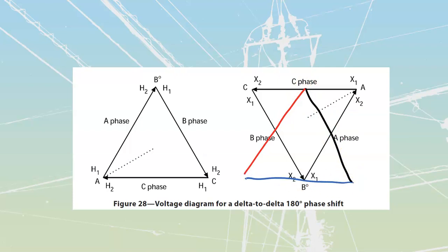If I take a look at that, I now see that on a standard system, here's where my line A is, and now I'm going all the way across from there to there if I were trying to parallel these together. This is going to be a catastrophic dead short. It's going to be roughly close to double your line-to-line value, and it will just destroy the transformers, switchgear, fuses, everything all at once. We just want to avoid that, and it's easy to avoid.